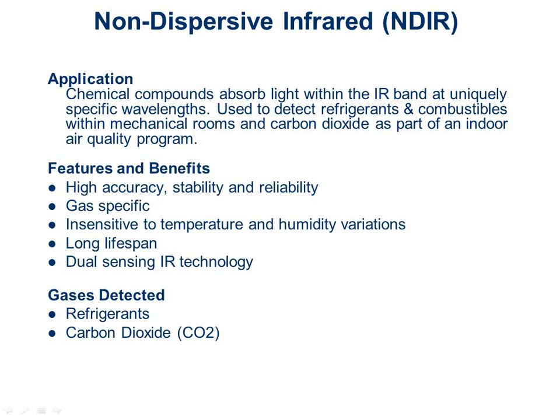And the outdoor ambient level stays the same all the time. It's the exact same parts per million. Over the course of decades, sure, it's been going up, but over the course of hours, weeks, days, years even, it's the same exact number. So if by your area it's 450 parts per million today, that's what it'll be tomorrow and the next day and the next day. So as long as the building goes unoccupied for a certain amount of time, that allows us to neutralize the building with the outdoors, and the sensor can self-calibrate back to those levels. So every night it can go ahead and do that.